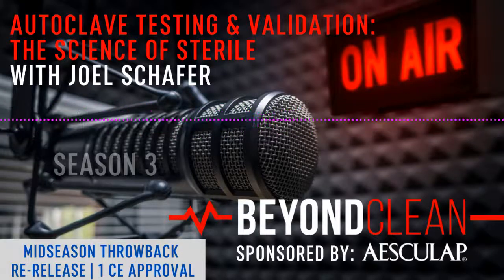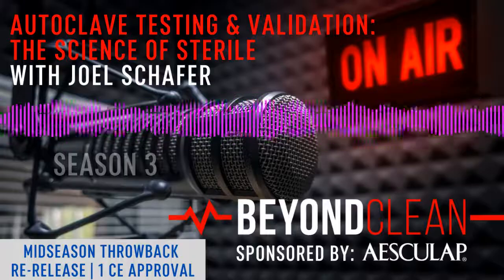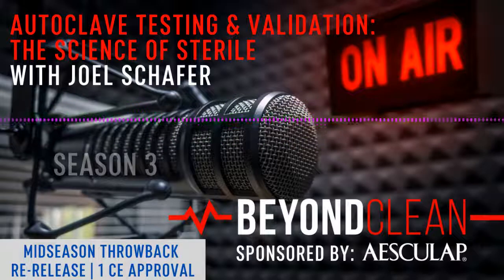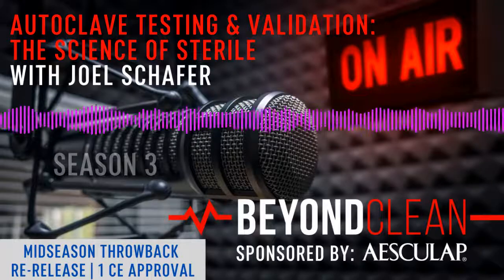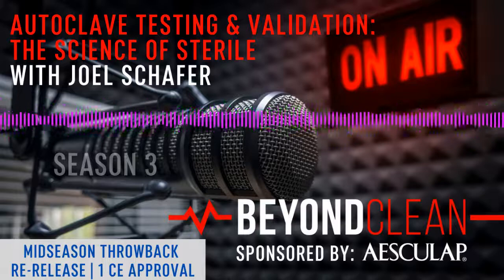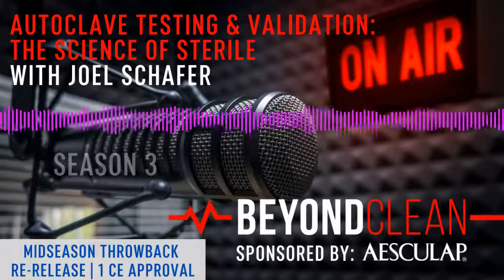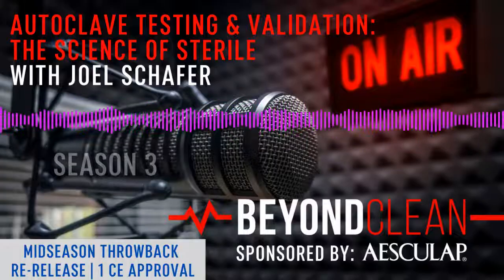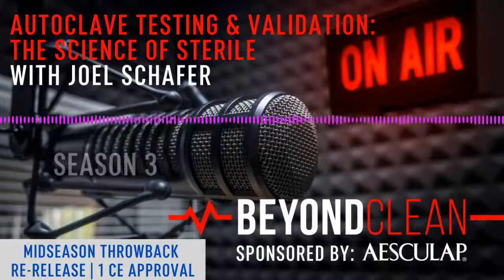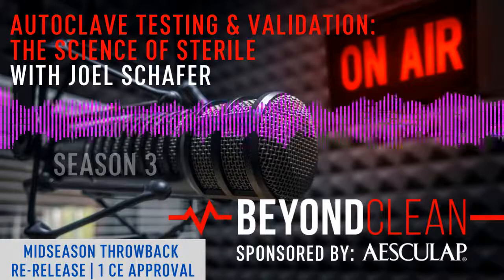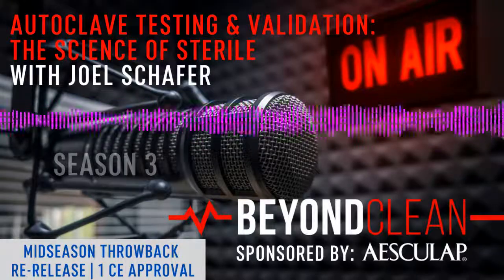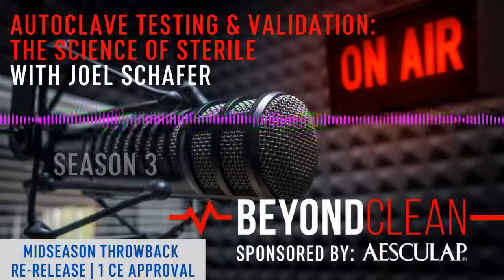So, Joe, obviously in the field, you're doing these validation tests on existing autoclaves that have been in use for a number of years. When you're testing an autoclave that has not been validated since it was manufactured, are you seeing a higher rate of failures, or are you seeing issues like the valve issues and other things come up that have been in use but not been caught yet? A lot of times we do. We typically get called in for the more common issues like wet pack, failed Bowie-Dick, things of that nature, and we help get to the root of the problem. If we haven't seen an autoclave before, I believe there's a 30% rate of issues such as the clock being off or the date being off, or that maybe it's getting hotter than it's supposed to get or not as hot as it's supposed to get for what it's programmed to.